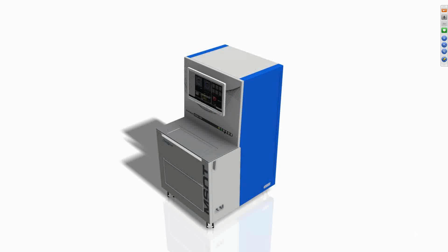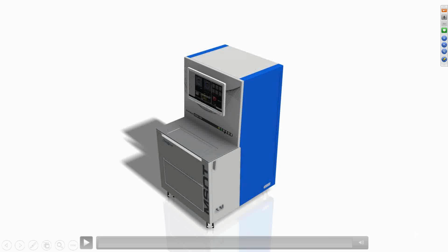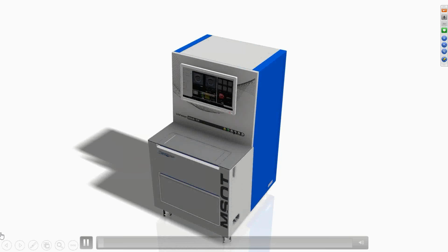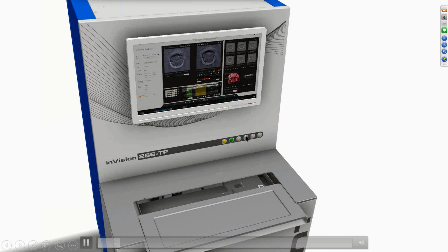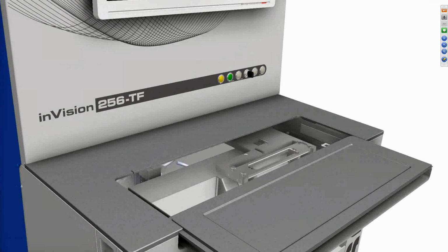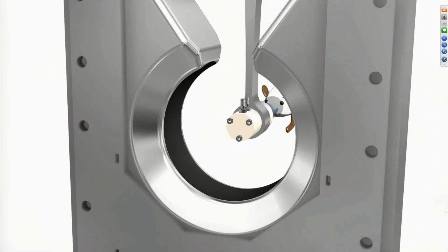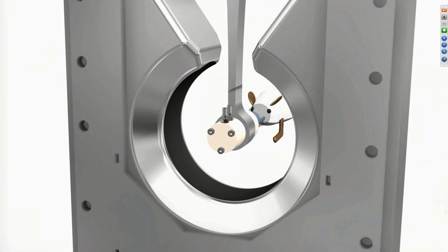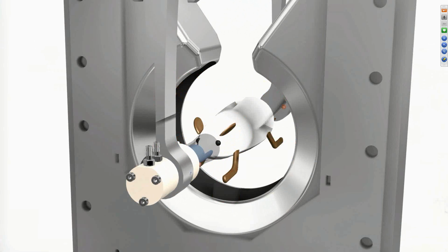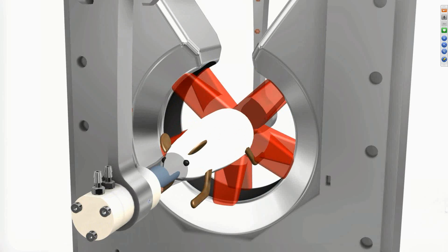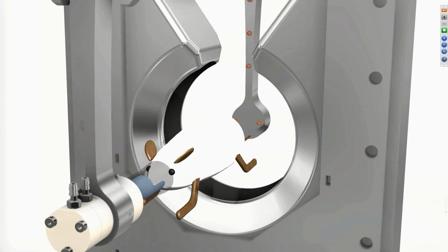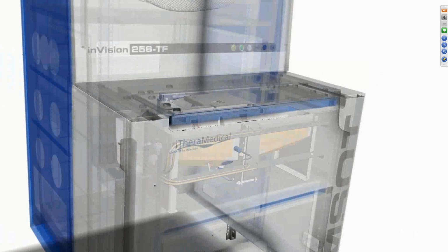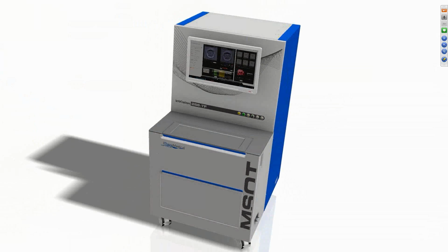This is a little cartoon about how an MSOT experiment would look. The system is a standalone system. The anesthesia would be connected in the bottom. And if I hit play here, we can see the mouse positioned in a specifically designed animal holder. The mouse is placed in the imaging chamber, and we can see the ultrasound transducer here in black. We move the mouse to the desired position. We illuminate all around the animal. This leads to the ultrasound waves, which we detect tomographically, and we then move the mouse forward to image the next body position. Those different cross-sectional images can then be stitched together in three-dimensional volumes.